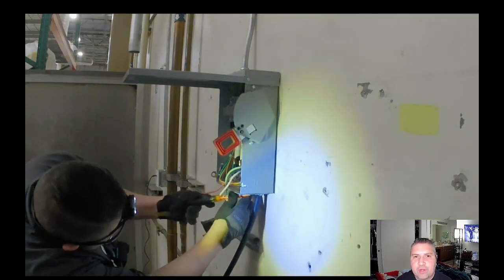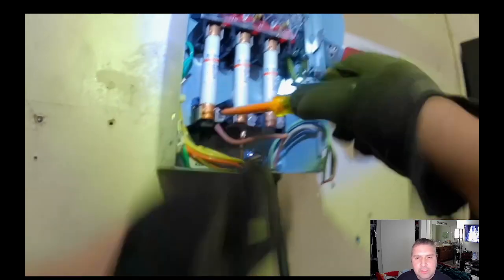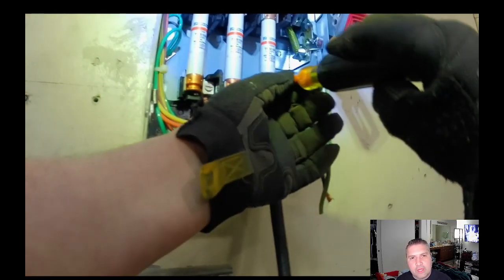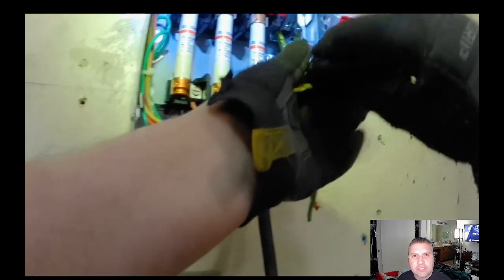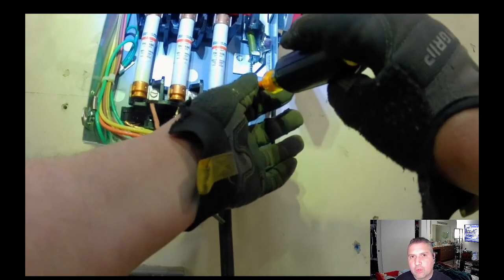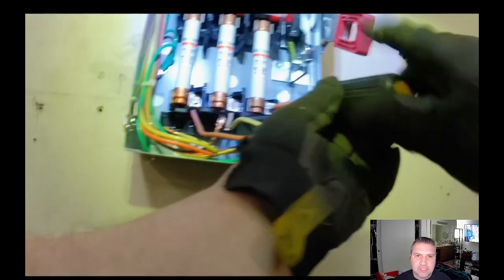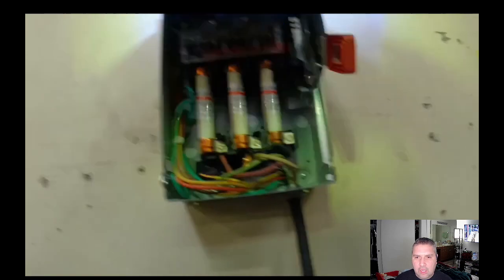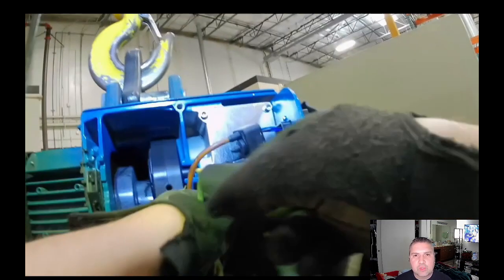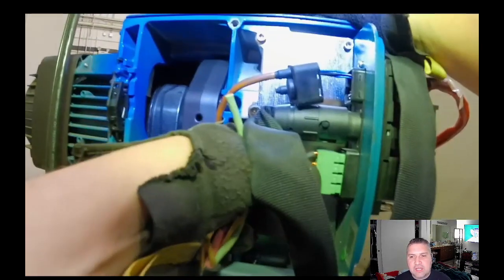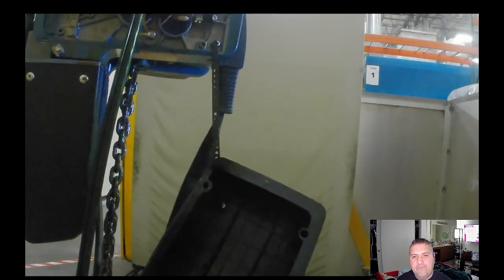So I set up this temporary whip just to get this thing powered in a remote location that was available at the time. This is 480 volt. I'm just wiring in this whip so I could get some power to this hoist so I can start testing operation and actually see what's going on with the hoist. And from that point, I'll make a determination on what I've got to do. Now I'm going to power it up.